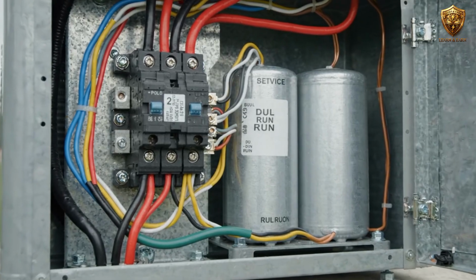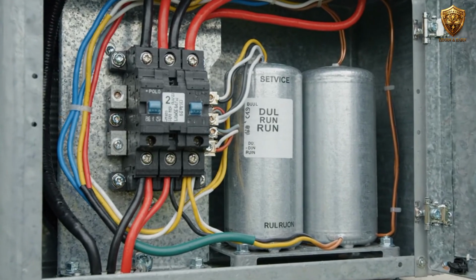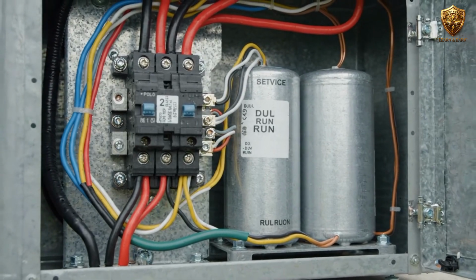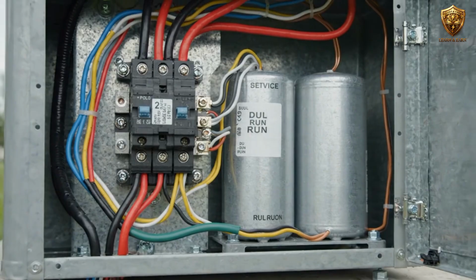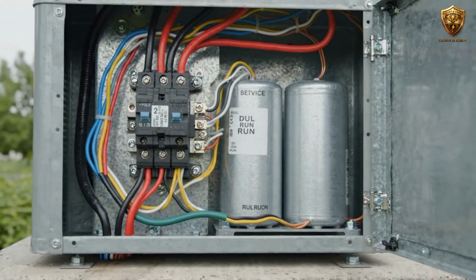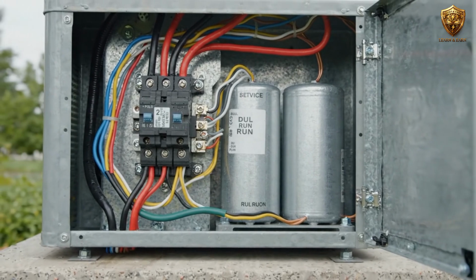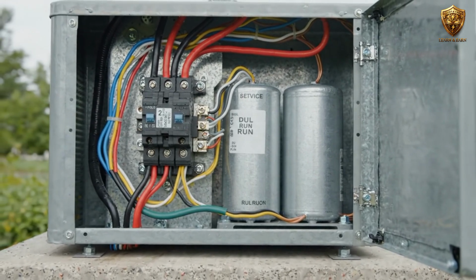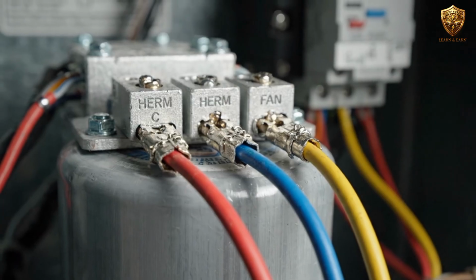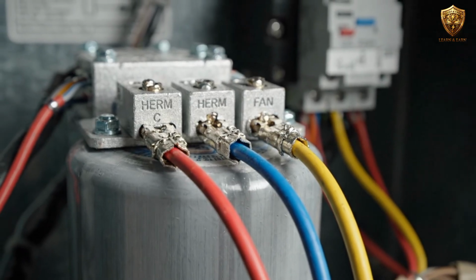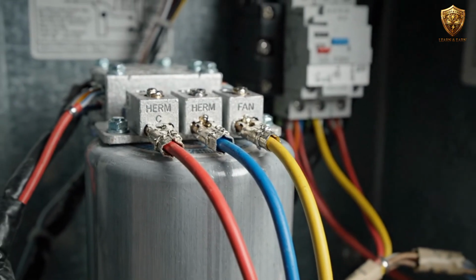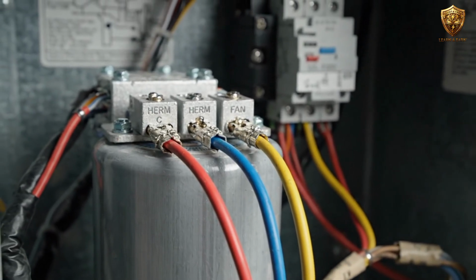Electrical problems are another major reason an air conditioner can stop cooling or fail to start. This is where a technician must slow down and test instead of guessing. A typical fixed-speed outdoor unit may contain a contactor, a dual-run capacitor, a compressor, a condenser fan motor, and electrical protection devices. Each component has a different job, and a failure in one part can create symptoms that look similar to another failure. Start by confirming the power supply and following the manufacturer's electrical diagram.